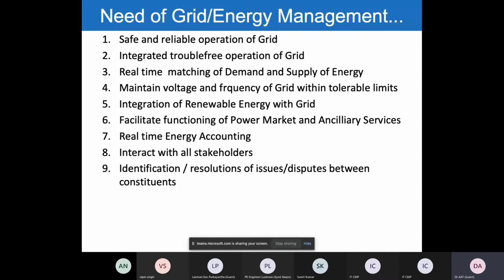And voltage and frequency, as I told you, can be maintained through active power management, by putting in more steam, more active power, and by increasing the excitation to maintain the reactive power, and thereby voltage. Then integration of renewable energy with the grid is becoming a major issue nowadays. You know that in India we have around 400 gigawatt installed capacity, out of which little higher than 100 gigawatt is renewable. So that means around 25%. But in energy terms, it is less than 10%.